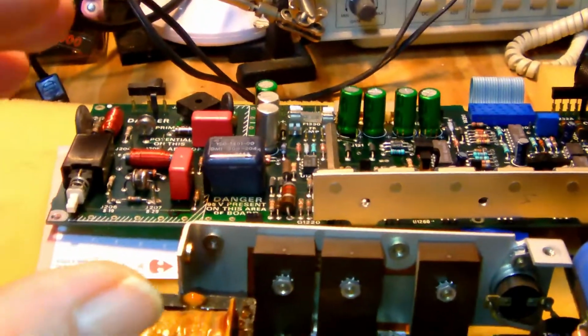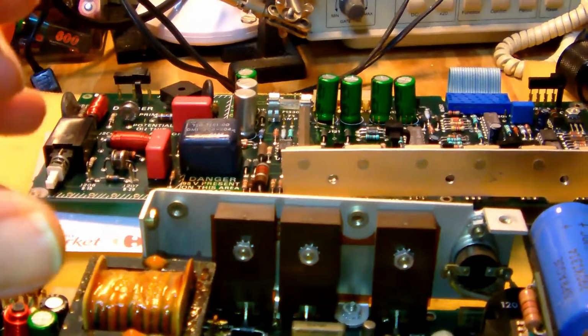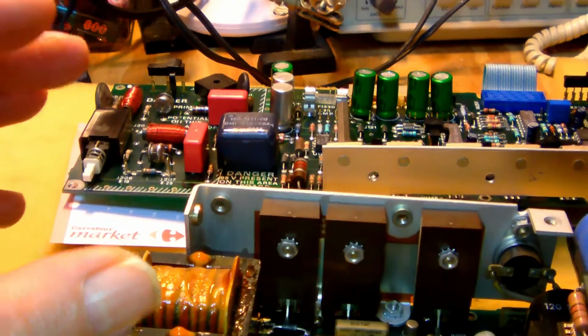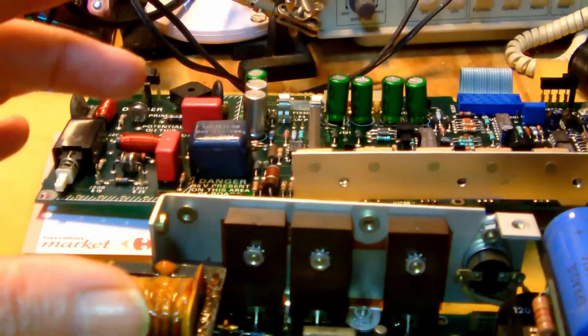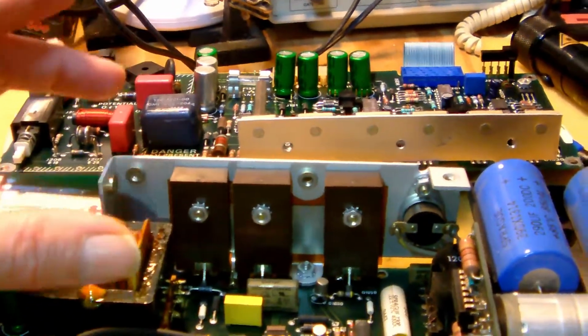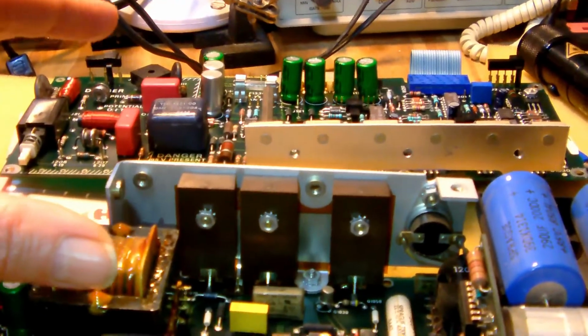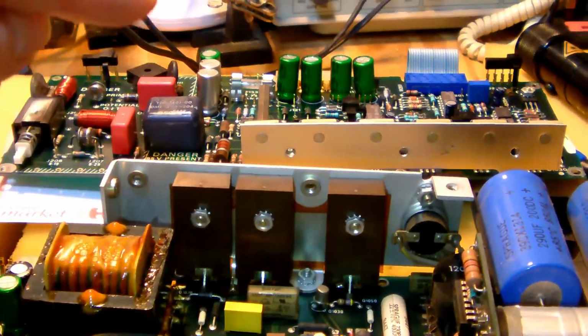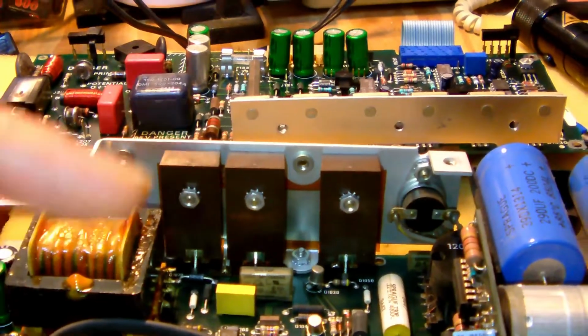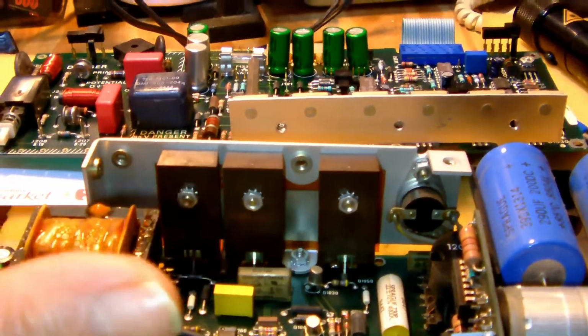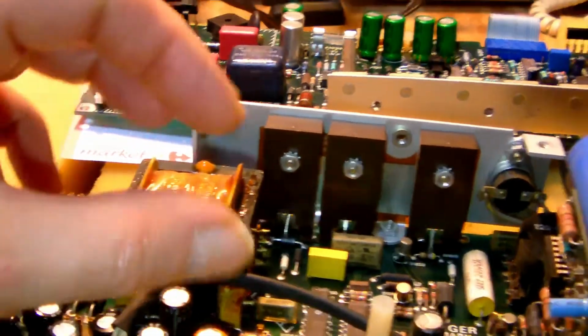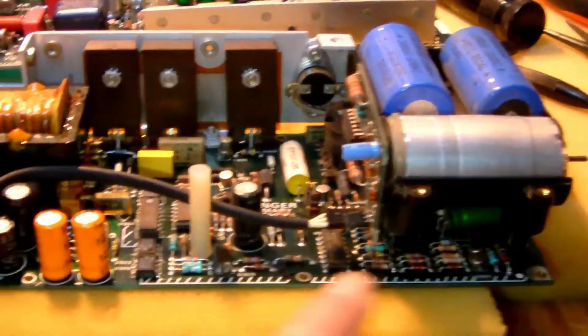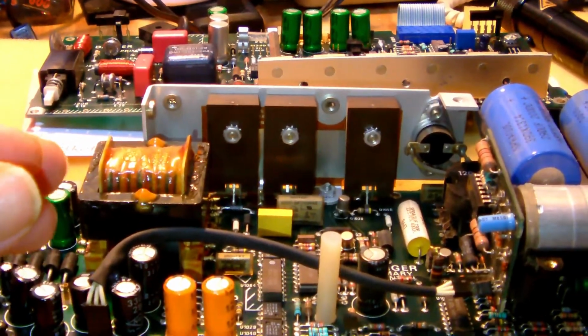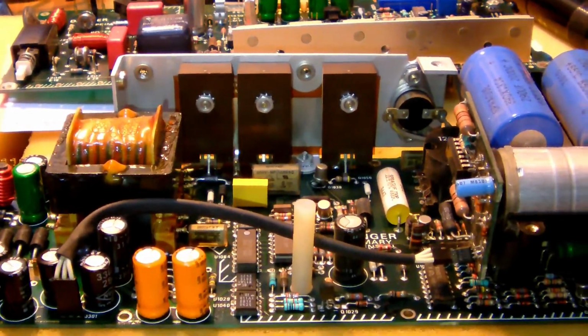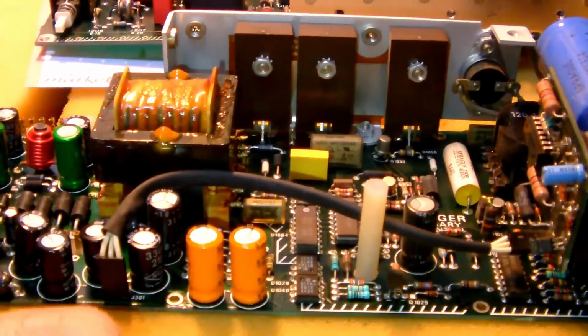Alright? But the reason for the confusion is that the engineers at Tektronix decided that they would split the logical power supply units, being the regulator board and the inverter board, over, let's say, two physical boards, and in effect, even though either logical part is not immediately related to the other. So yeah, they were hampered by the physical length of a PCB, and they couldn't just fit the parts that should be logically located together on one PCB. They had to split it over two.